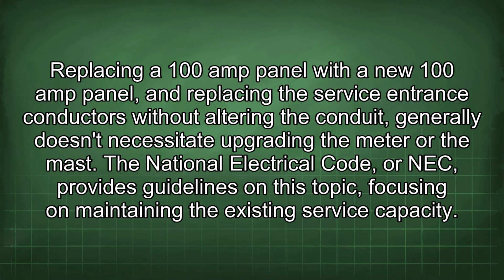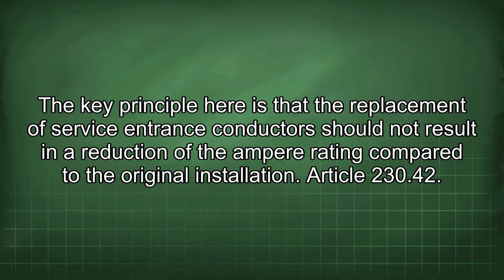Replacing a 100 amp panel with a new 100 amp panel, and replacing the service entrance conductors without altering the conduit, generally doesn't necessitate upgrading the meter or the mast. The National Electrical Code, or NEC, provides guidelines on this topic, focusing on maintaining the existing service capacity. The key principle here is that the replacement of service entrance conductors should not result in a reduction of the ampere rating compared to the original installation.